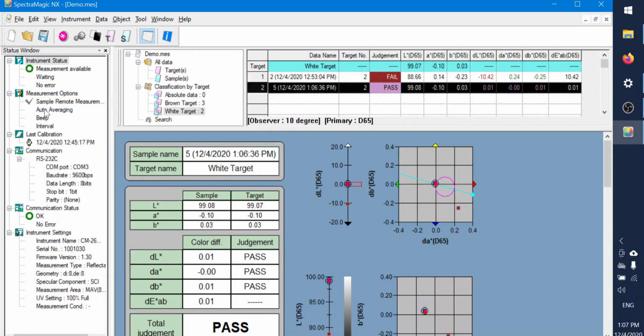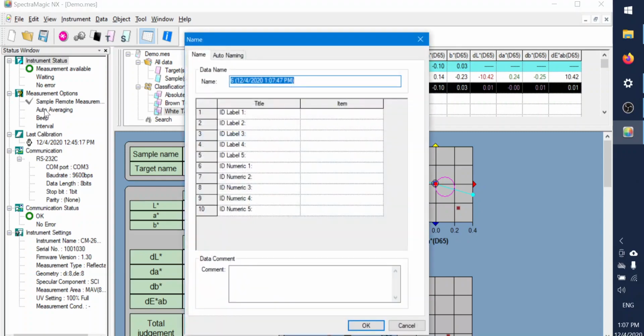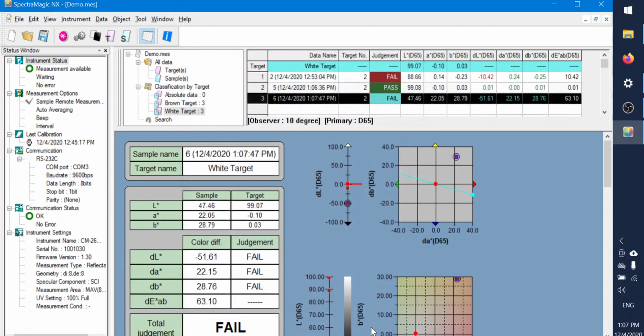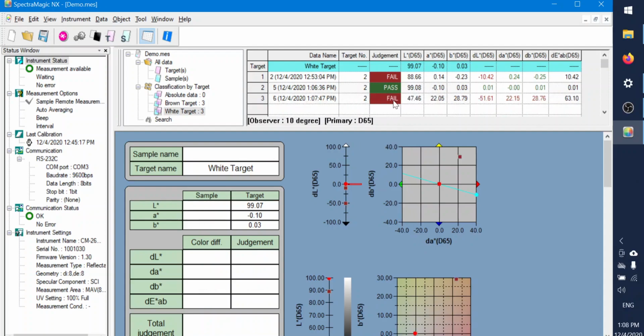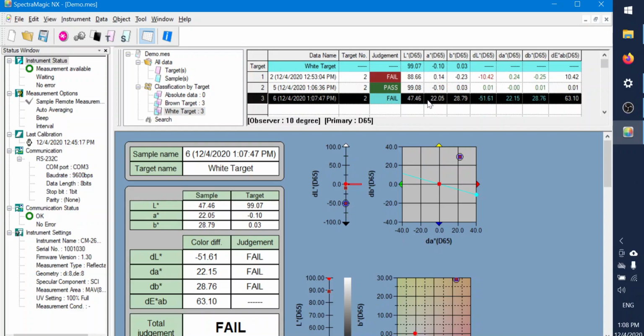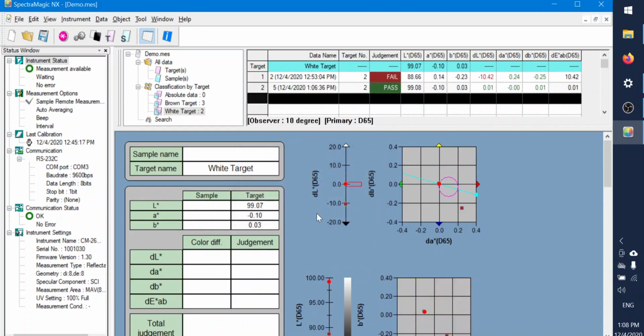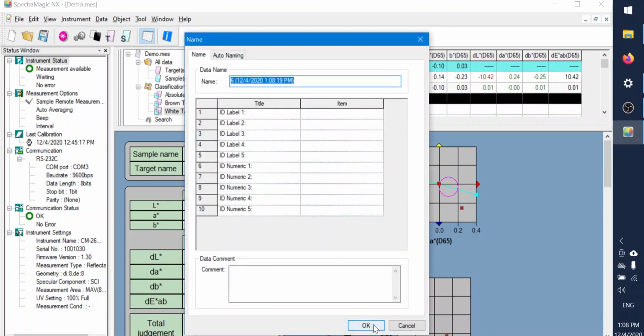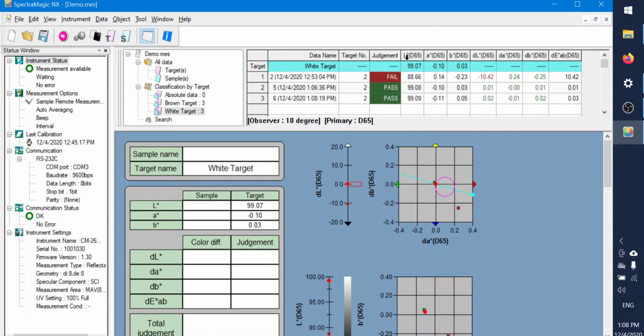So now when I actually click the measure button on the instrument's hardware, it will have a display saying receiving data, and I can give a data's name. If I would not like to keep the name and leave it as default, I will just click OK. And oh yeah, I measured it on the wrong color, so hence why the data is failed. So since I do not want this measurement, I will just right click this and click delete. It will delete this measurement data. I will place it back on the sample. Click on the measurement, click on the instrument hardware. Again it will say receiving data, and will use this sample default's name. Yep. And then it has transferred the data from the instrument to the software.